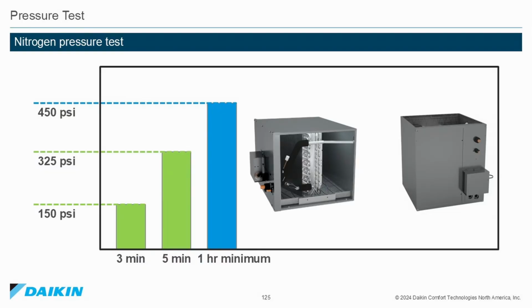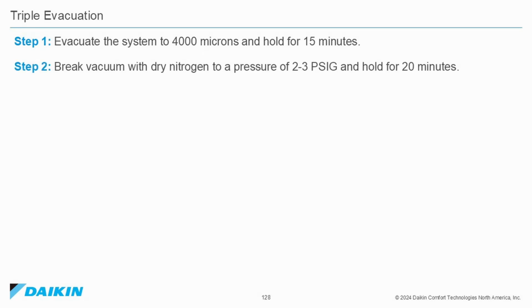After the pressure test has verified that there are no leaks, a triple evacuation should be performed. Step 1. Evacuate the system to 4,000 microns and hold for a minimum of 15 minutes. Step 2. Break that vacuum with dry nitrogen to a pressure of 2 to 3 psi and hold for 20 minutes. Step 3. Evacuate to 1,500 microns and hold for 20 minutes.